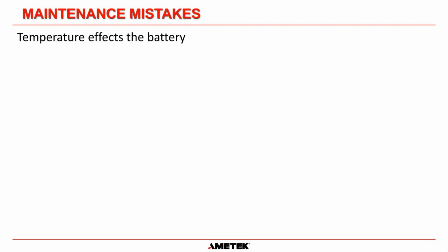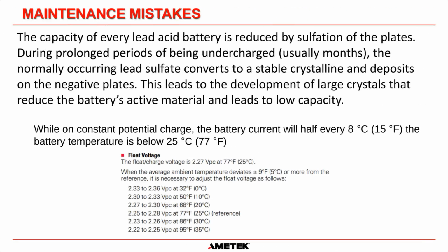Another maintenance mistake is people don't realize that temperature affects the battery. The capacity of every lead acid battery is reduced by sulfation of the plates. That's how you lose capacity, is sulfation of the negative plates. So during prolonged periods of being undercharged, it could be weeks or months, not days, the normally occurring lead sulfate converts to what's called a stable crystalline and deposits on the negative plates. And that leads to the development of large crystals that reduce the battery's active material and leads to low capacity. So basically, sulfation of the plates causes low capacity inside a lead acid battery. So if you are undercharging a battery, then you are allowing the lead sulfate to build up.